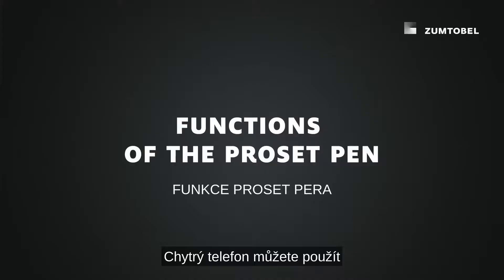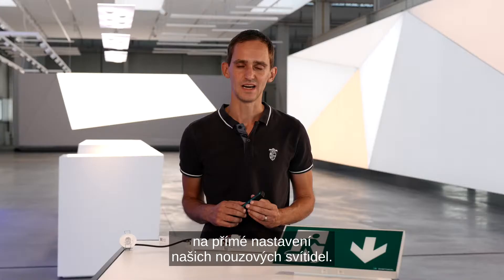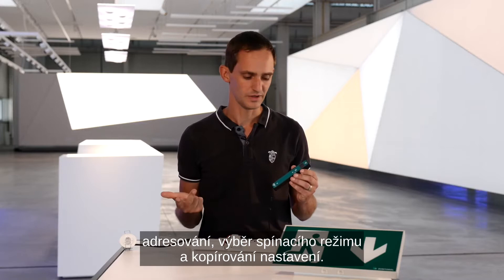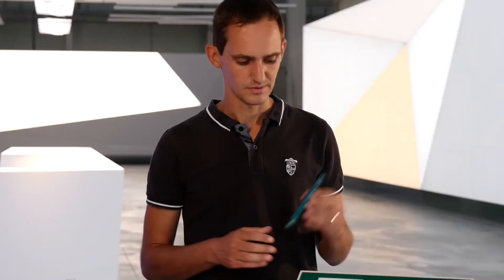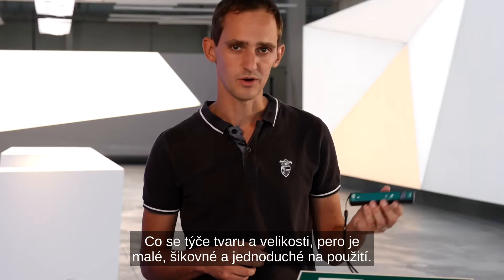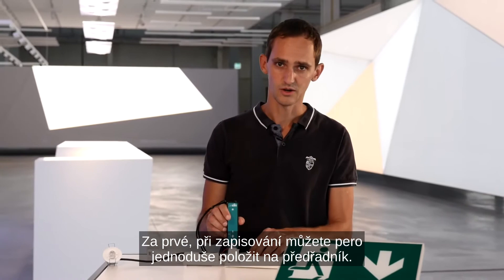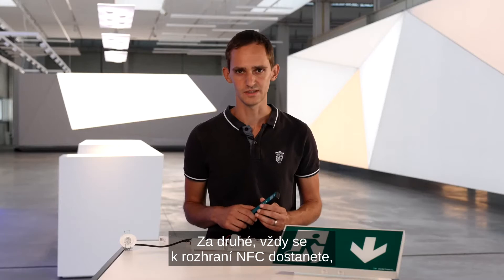You can also use your smartphone directly to configure our emergency luminaires. The ProSet pen is an alternative if you want to use a small, robust, and industrial tool. The main functions integrated in the pen are addressing, selecting a switching mode, and copying a configuration. Regarding the form factor, the pen is small, handy, and easy to use, and this pen-like shape has different advantages: during writing you can just put the pen on the ballast, and you always have access to the NFC interface inside the luminaire no matter how slim the luminaire housing is.